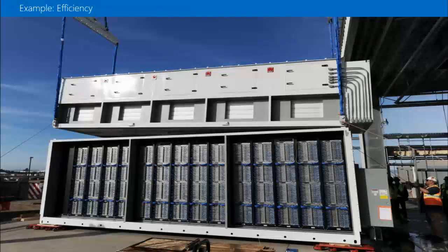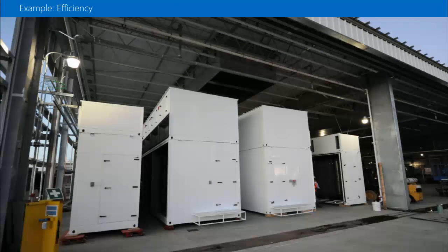So, it's really built, it lives in a really big shed like that. No walls needed. We do build a roof over the top to try and keep the harshest elements out of it. But then you can see on the front there an evaporative cooling unit that plugs in the front, and then an air recycling unit that, as the air handling unit pumps out the air, pulls in some of that hot air to keep a consistent temperature moving through those servers as well. So that's essentially a Generation 4 container. That's what a data center looks like these days rather than a really big building.